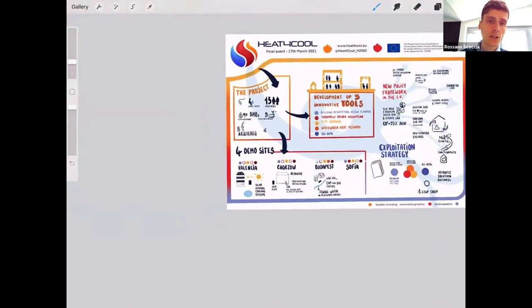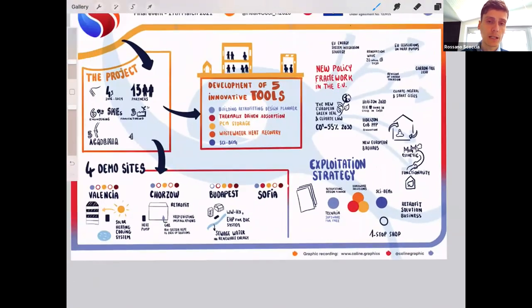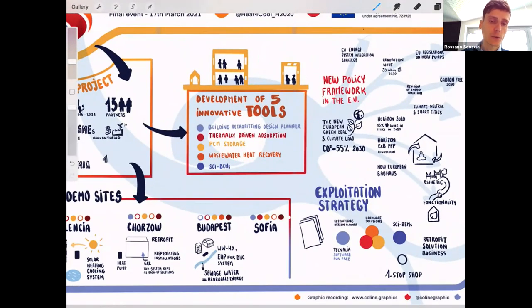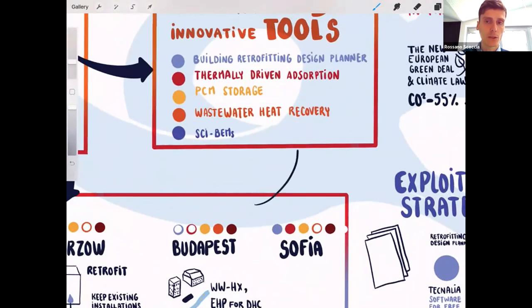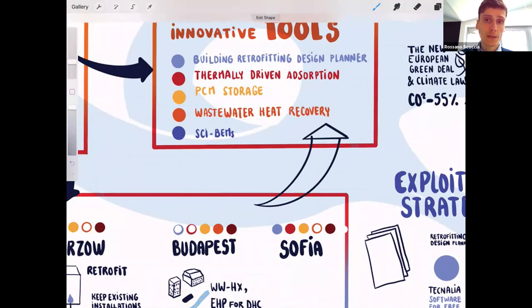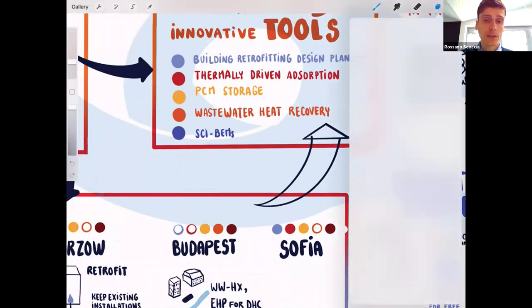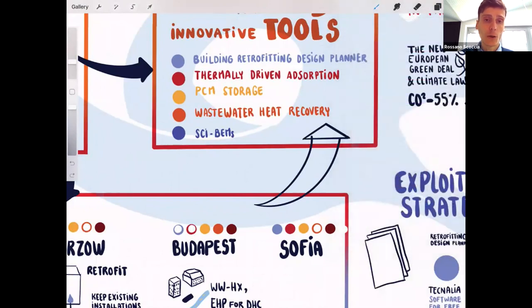Yes. Unfortunately, the COVID emergency changed a lot of our plan for the monitoring activities. We had some delays in the installation of the instruments and the checking of them because we couldn't go to the pilot sites. And moreover, it changed a lot how the buildings were used. For example, Valencia is a building with a lot of apartments used for tourism, and we had low occupancy during the summer. The same happened in Budapest for the district system, with needs which were lower than expected. So, yes, the COVID emergency changed how the buildings were used.